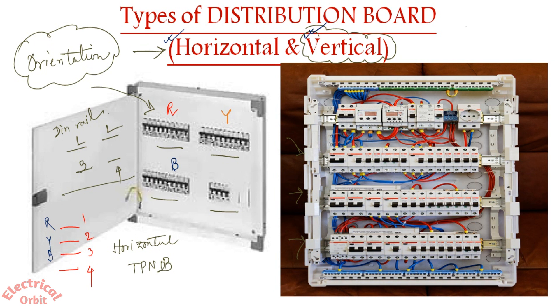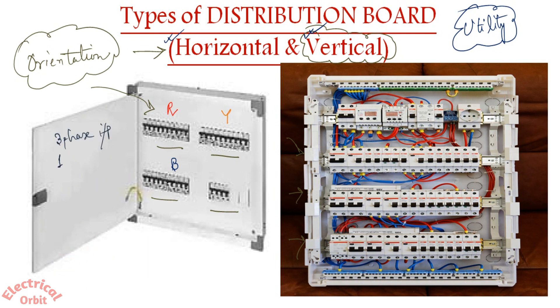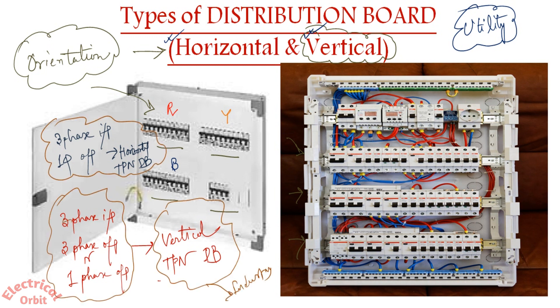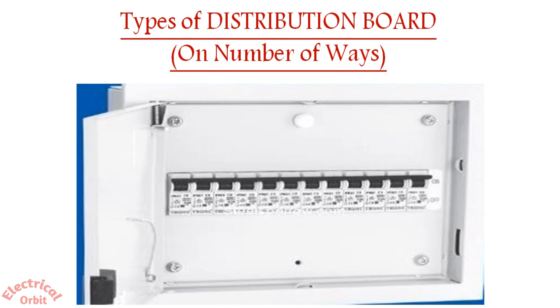The difference between horizontal and vertical TPN DB comes down to their utility in industry. Whenever you want three-phase input and single-phase output, go for a horizontal TPN DB. If you require three-phase input with three-phase output or single-phase output as well, then go for a vertical TPN DB. This is the design approach as per industry practice.